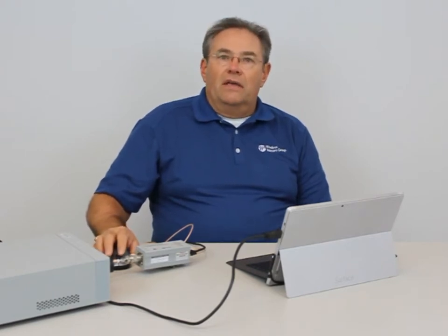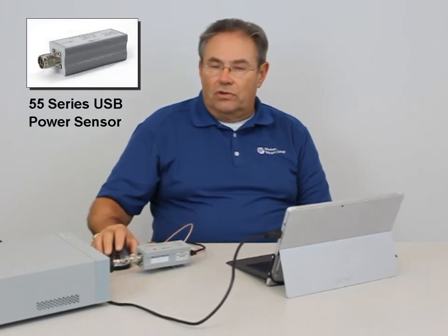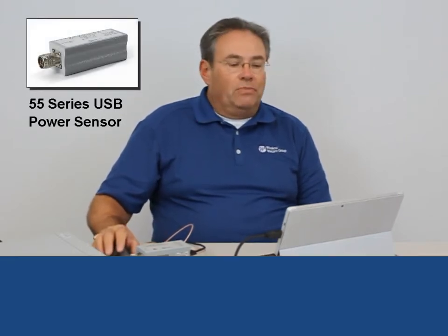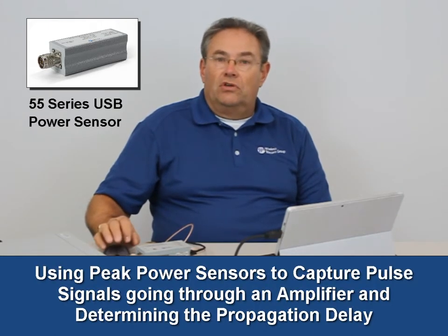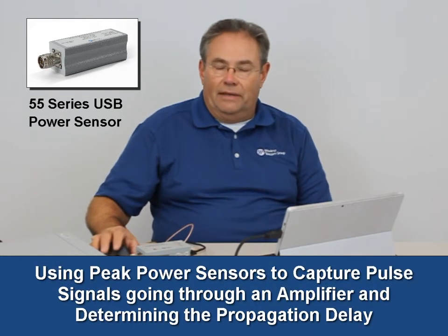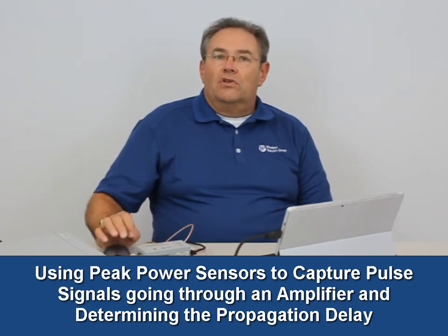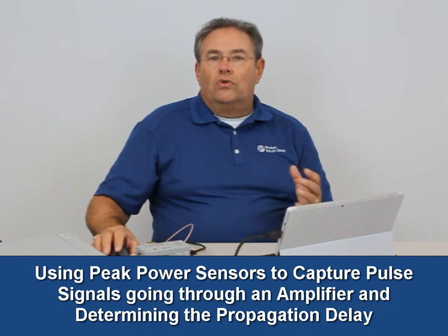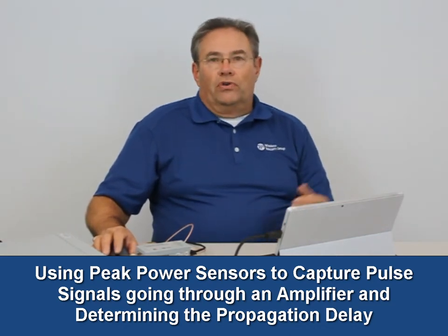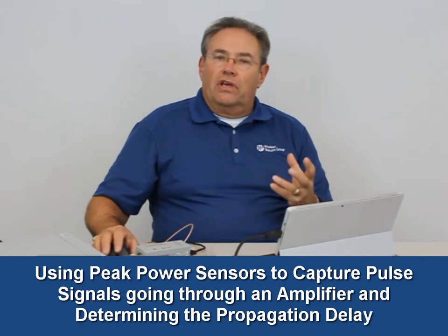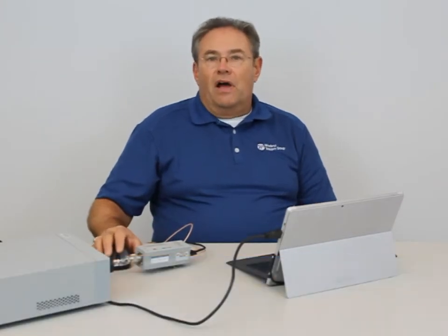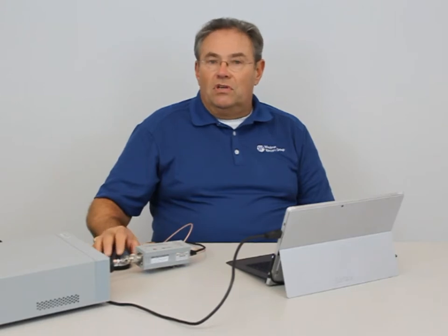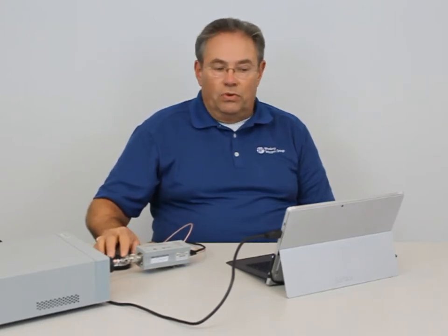The topic of today's video is going to be how to use peak power sensors, RF sensors, to capture and look at pulse signals going through an amplifier and determining the propagation delay. This is an important topic now these days with distributed antenna systems, where we're doing active and passive DAS, where you're taking an electrical signal, converting it to an optical signal, and back to an electrical signal. Amplifier delays can then become cumulative, causing issues in your signal distribution.